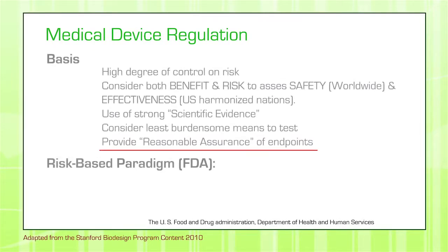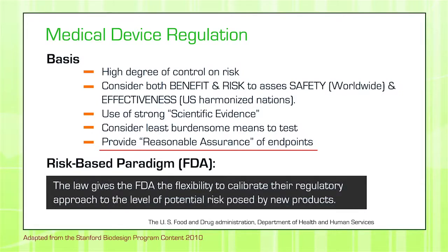And finally, one of the basic principles of medical device regulation is to provide reasonable assurance of these endpoints, which is something particularly related to the design of medical protocols and clinical protocols for testing. But you should know at this point that the creation and calculation of an N, a number of patients required to create statistically significant data, is what is important in providing reasonable assurance of your endpoints.